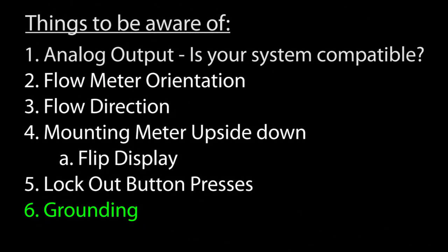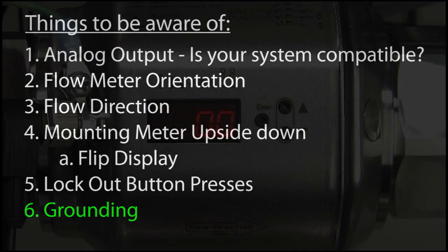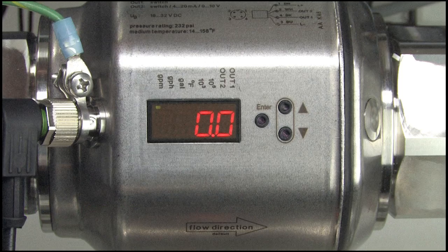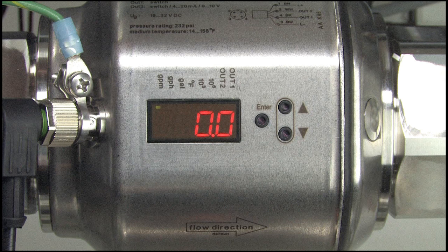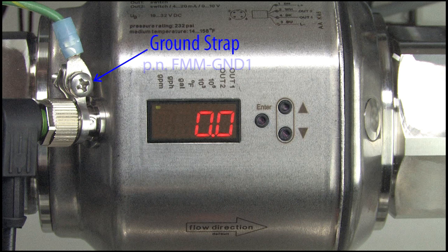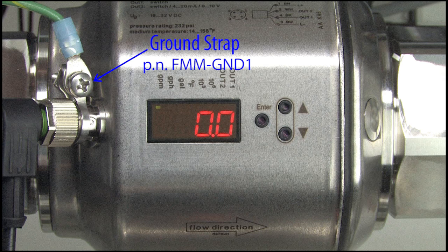This is a class 3 device so the power supply doesn't have to be grounded. But the flow meter itself does need to be grounded, so if you put this in line in a PVC pipe system for example, be sure to run a ground wire from the unit. AutomationDirect has a convenient ground clamp for this if you need it.